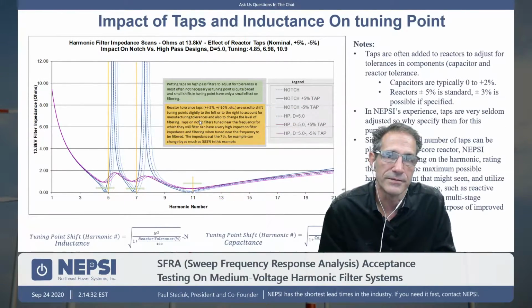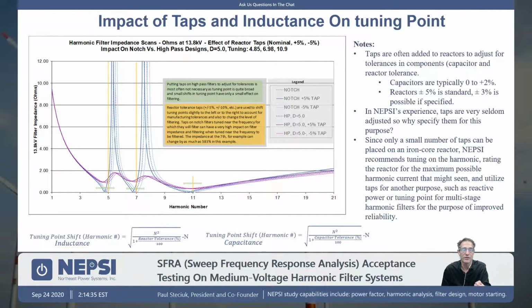And then we have, well, what do changes in inductance mean? And what might changes in capacitance do? These changes or errors that might occur, and again, it could be a missed nameplate capacitor, a partially failed capacitor, an improperly tapped reactor, an improperly designed reactor, a misplaced reactor within the system itself. There's a whole host of manufacturing errors, from our component suppliers as well as from us inside our own factory, that can result in a shift in the tuning points. So changes in inductance, changes in capacitance or capacitor reactance result in a shift to the left or to the right, and we are able to identify these errors very easily with this test system.